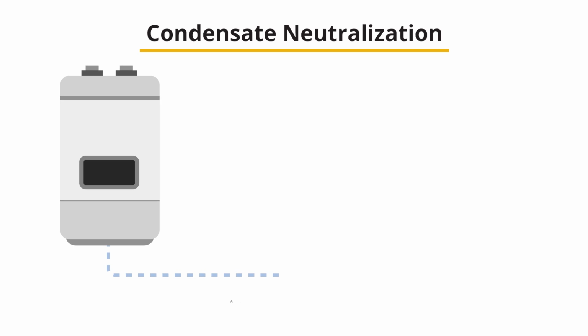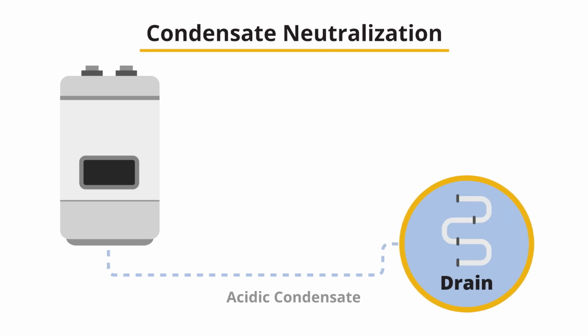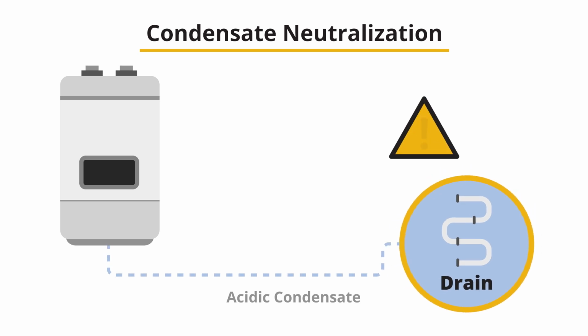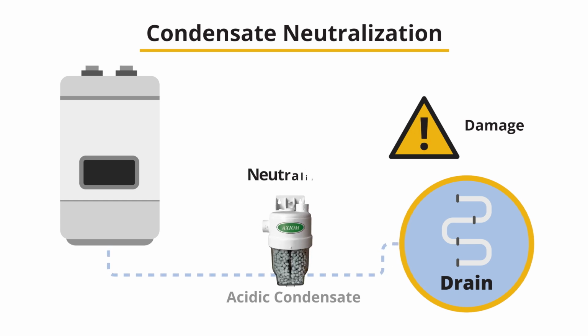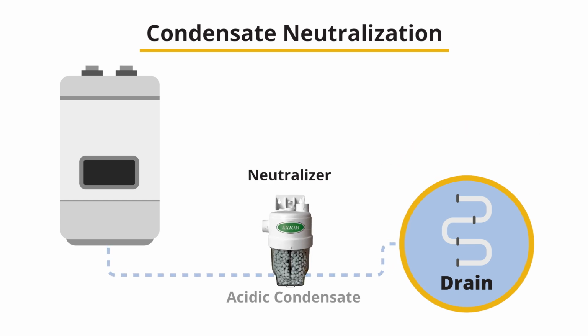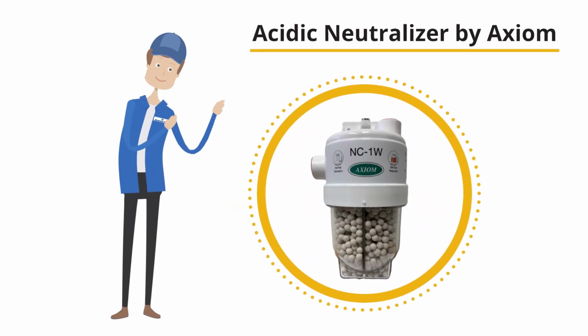Because these boilers are so efficient, condensate is extracted from the boiler's flue gases and eventually makes its way through the boiler and down into your house drain. This condensate is acidic and can cause damage to your drainage system, which must first be treated before going down the drain. For this, we use an acidic neutralizer by Axiom.